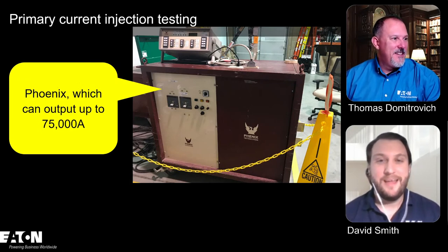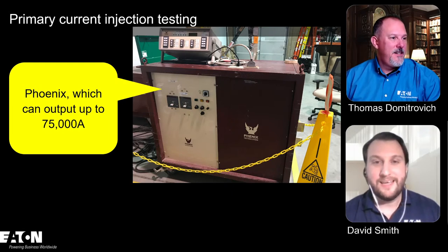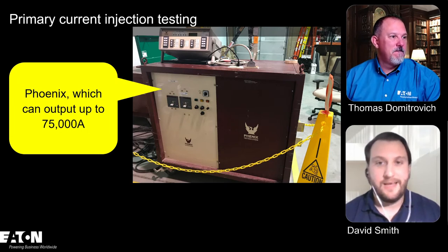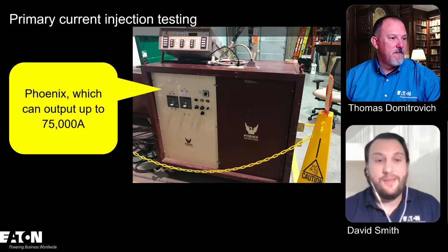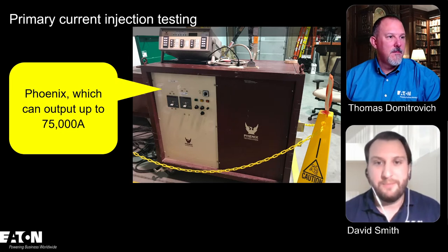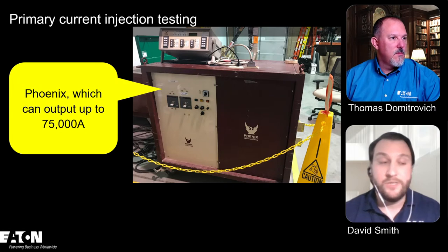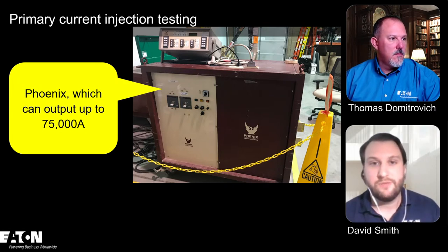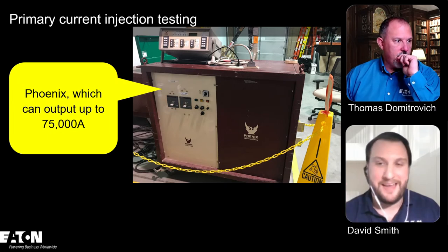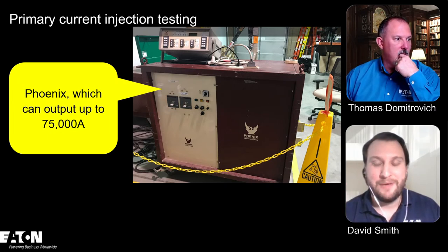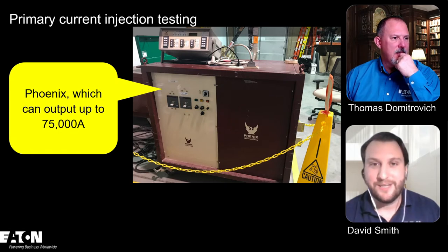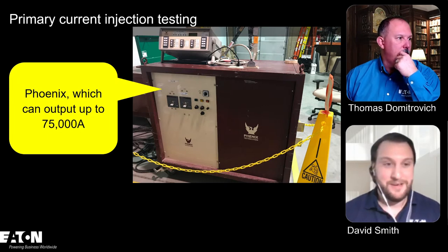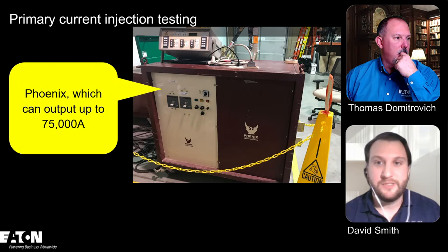Right. I think this is at the PSEC up in Warrendale, Pennsylvania. This thing is pretty big. And if you're taking it out to the field, you might need three phase. You might need some type of source power to be able to run this thing just to test your breaker, which could not be an issue, or it could be an issue for you. On top of that is one of the pieces of equipment that we use for secondary current injection testing. Typically secondary current injection testing comes with something that is the size of a suitcase, and you just need simple 125 volt power to be able to do that.